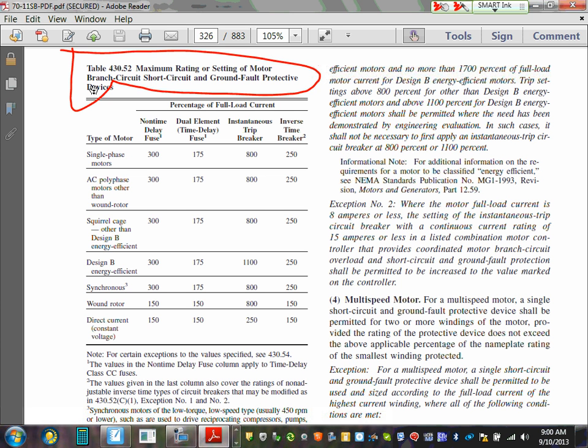I want to bring to your attention, guys, circuit breakers. These are my circuit breakers, inverse type circuit breakers. There are two types of fuses, either non-time delay fuse or dual element time delay fuse. And sometimes you might have instantaneous trip circuit breakers, but I'm not going to talk about that one. So you have a choice to make: which type of overcurrent device do you need to use? I want to use inverse type circuit breakers. These are called inverse type circuit breakers. That's what I want to decide.